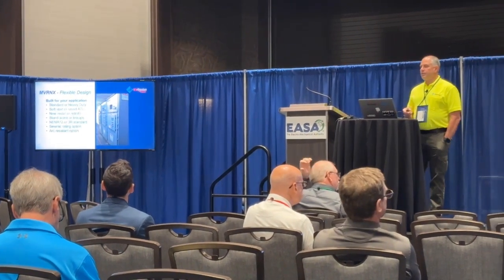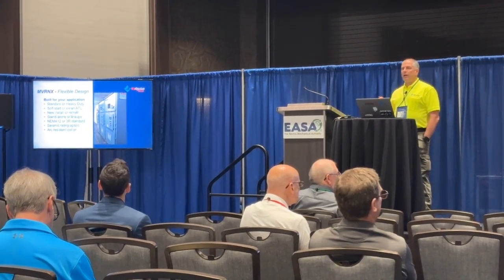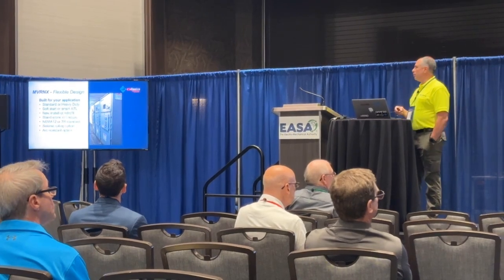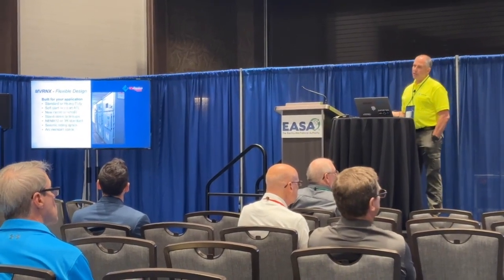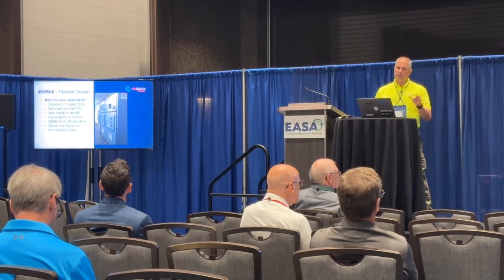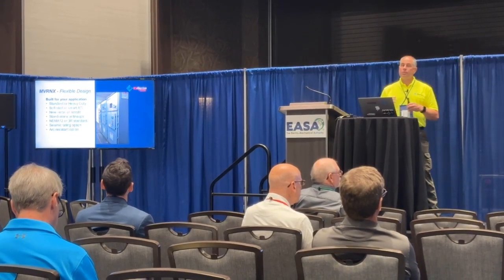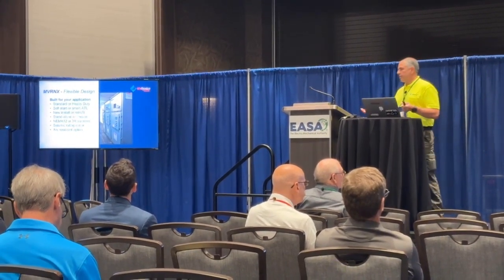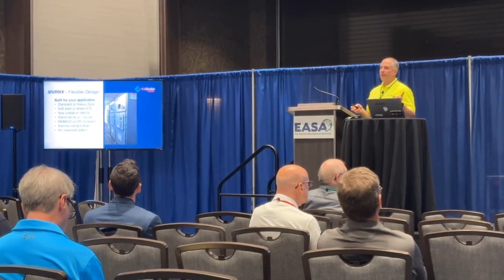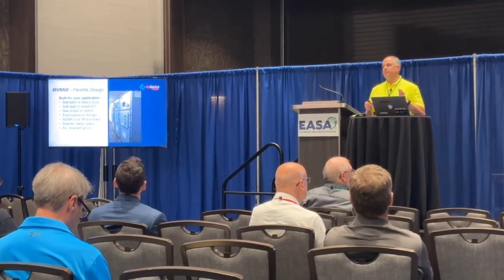These are set up for standard, heavy duty use, and we've completed all the arc flash testing. For those not familiar, arc flash testing makes the unit totally safe for anyone standing in front of it — if an arc flash or explosion occurs, it vents through the roof of the starter, and none of it is felt by personnel standing out front.